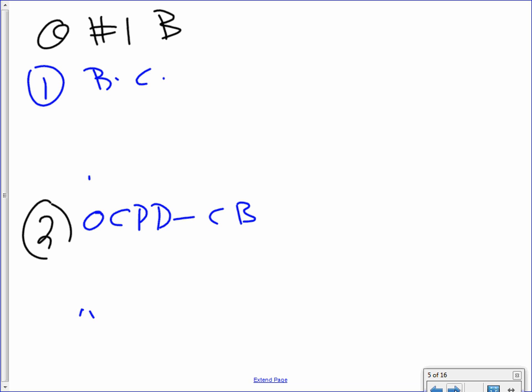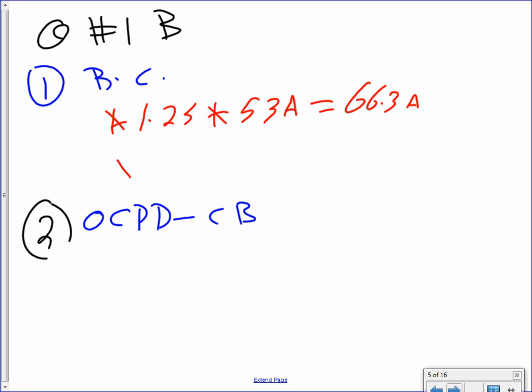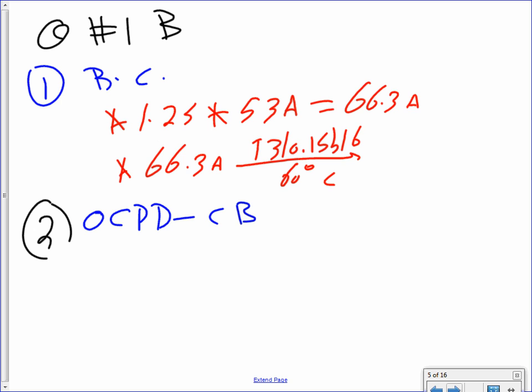I have my second furnace, guys. Let's go size the same process. You guys can go right before me even. Same process for the second furnace. The second furnace, guys, 1.25. You can times it by 53. 53 amp, because that's the amps for this boy. 66.3 amps. Then you take your 66.3 amps, take it to table 310.15 B16 under 60-degree column. We know why, right?